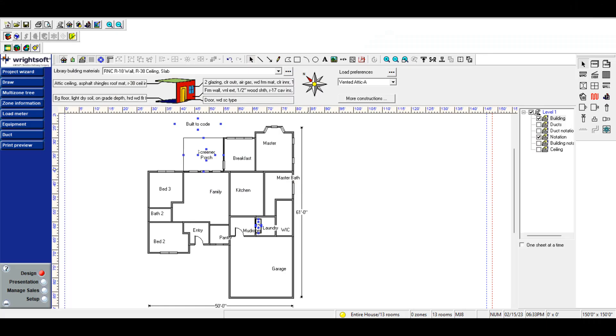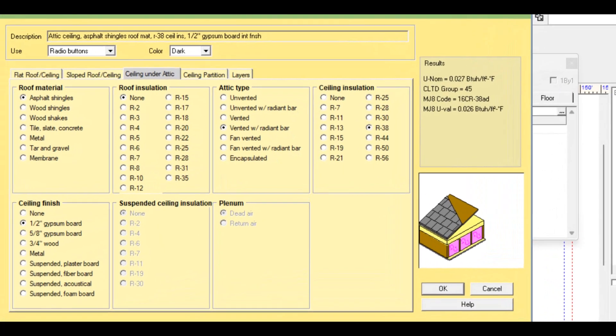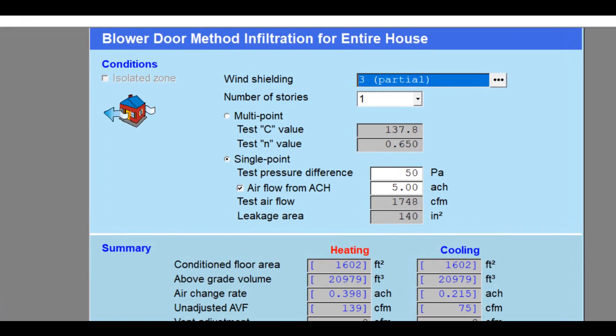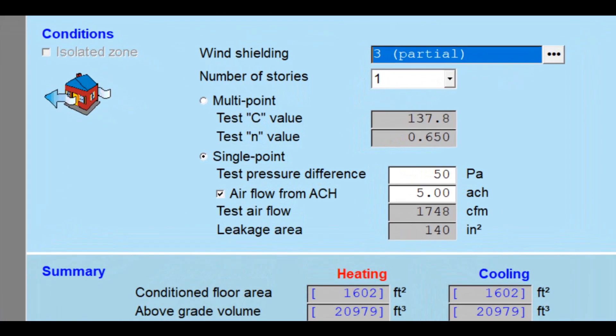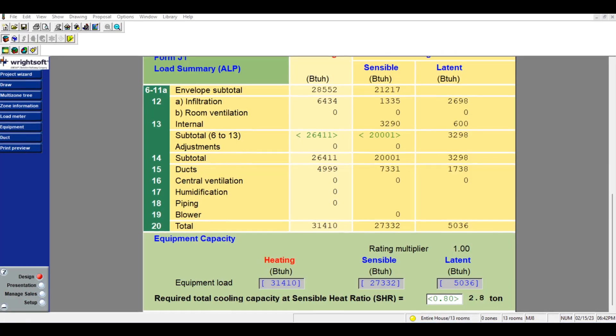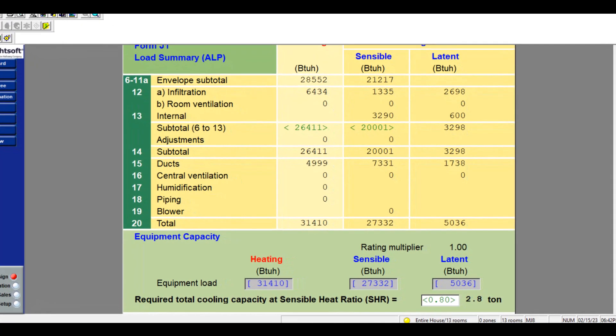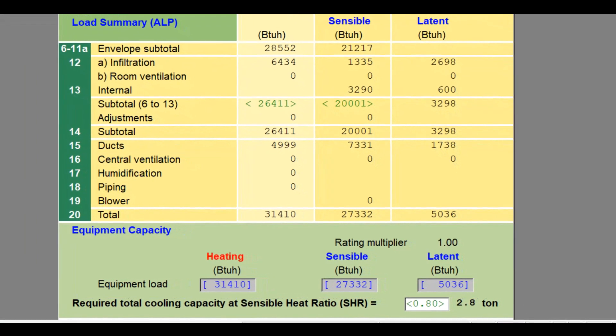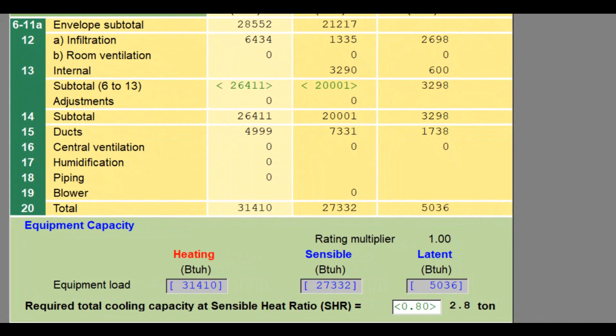The first thing I did was model the house on Wrightsoft, which is my HVAC design program of choice. This house as built to code would have R38 blown insulation in the ceiling and be a typically leaky house — about 5 ACH. The total load usually comes out to around 2.8 tons. Interestingly, the HVAC contractor that normally does the installs on these houses puts in a three-and-a-half ton unit.